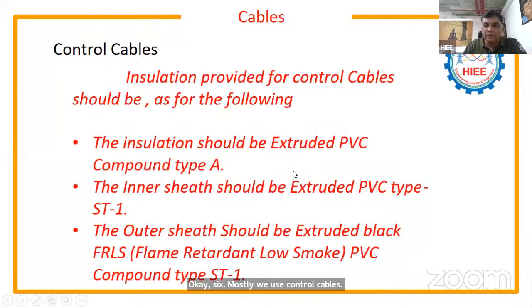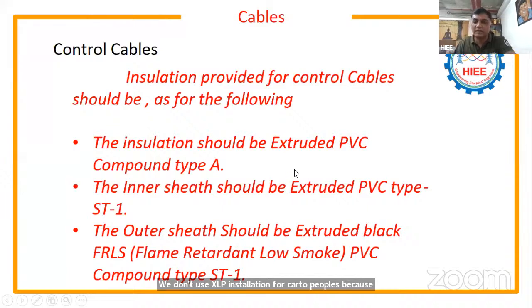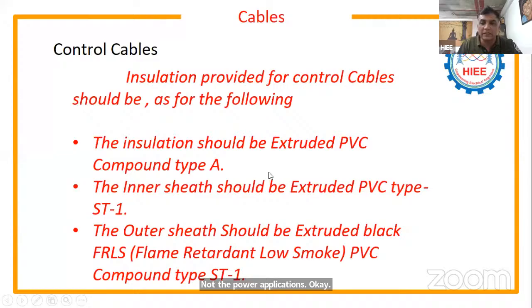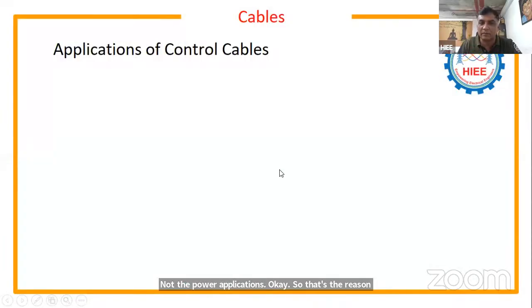And I told you the outer insulation of control cables will be PVC insulation. We don't use XLPE insulation for control cables because control cables are used only for control applications, not power applications. That is the reason we generally use PVC insulation for control cables.